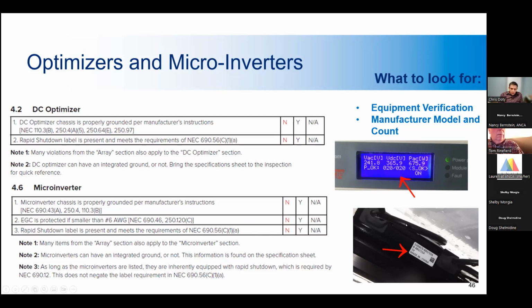Here we have a quick look at the checklist for the optimizers and inverters. Both microinverters and optimizers give module level control, so they have similar requirements in the code. It's easy to go through and make sure that everything is accounted for in the checklist. The checklist looks for not only equipment verification, but also other details such as conductor type, proper grounding, etc.